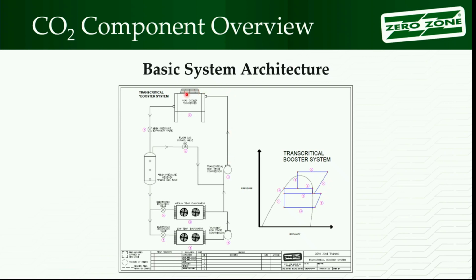We go up to a gas cooler. Come out of our gas cooler, got our high-pressure expansion valve. So higher pressure at the gas cooler, lower pressure in the tank. This valve's going to maintain the pressure. It's getting a signal, so it controls the pressure in the gas cooler. For the most part, it doesn't care what's going on in the receiver. Flash gas valve really cares about what's going on in the receiver. It's looking back and it's getting a control to maintain that.